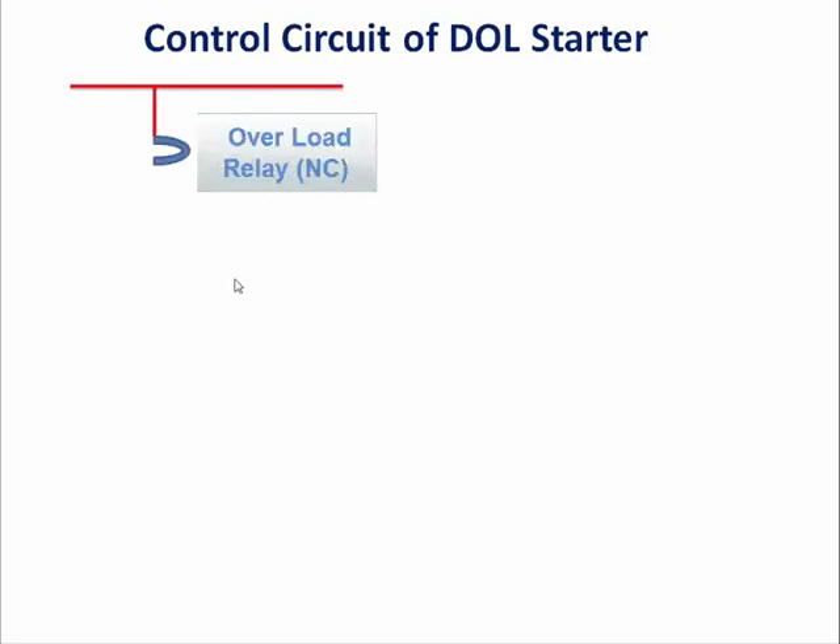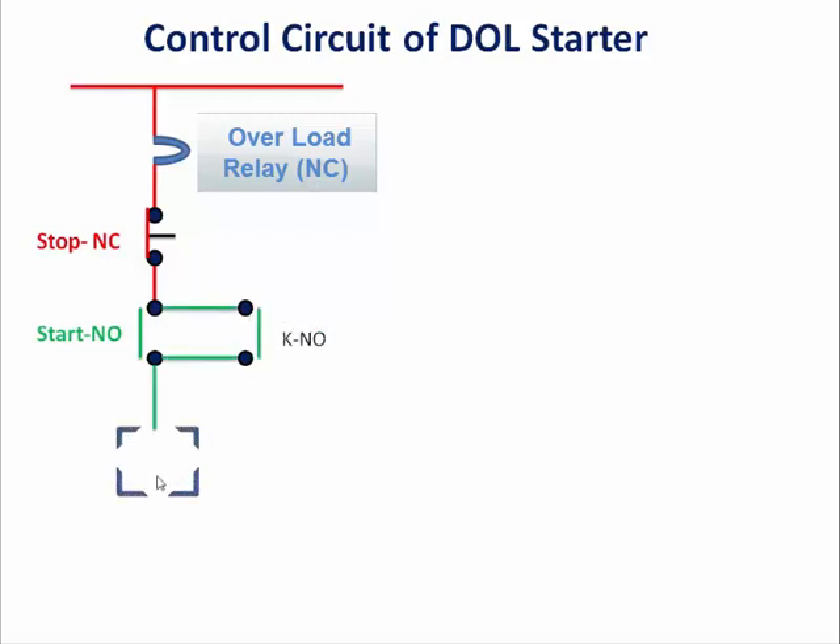So now we will talk about the control circuit of the DOL starter. First we will connect with the phase, overload NC contact, then stop NC contact, and after that start NO contact and parallelly contactor NO contact, and last we will connect the contactor with the neutral.